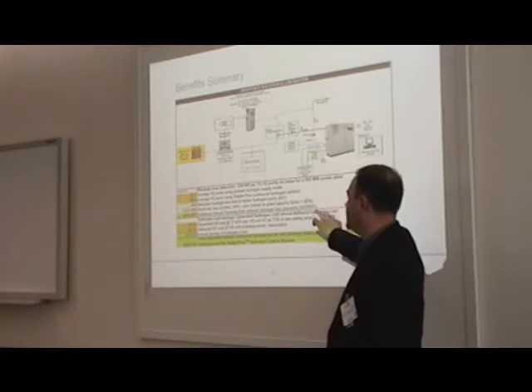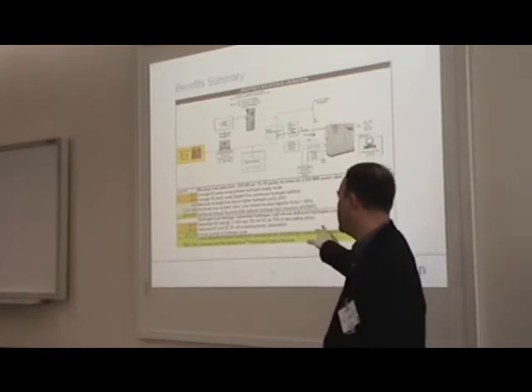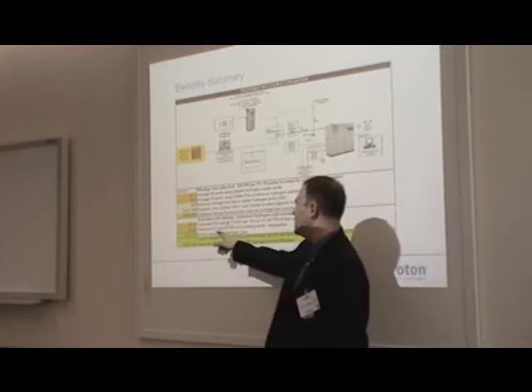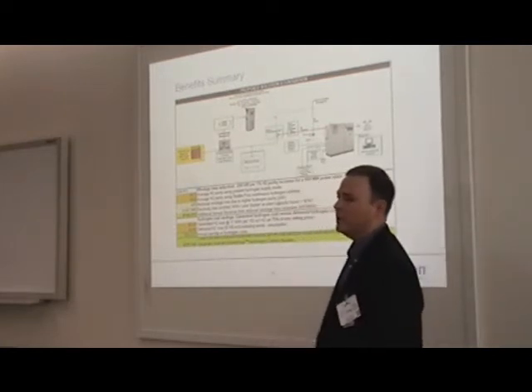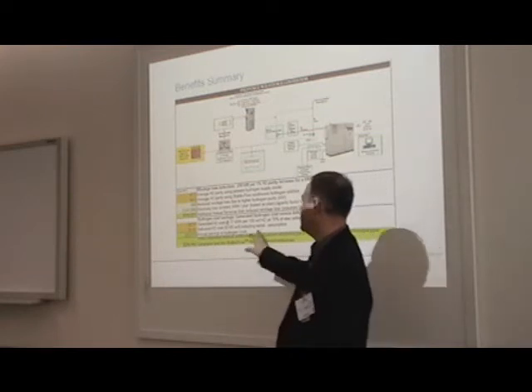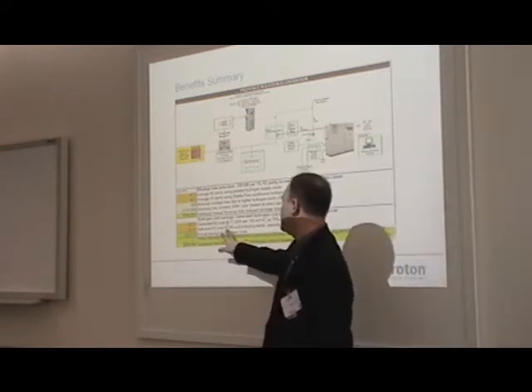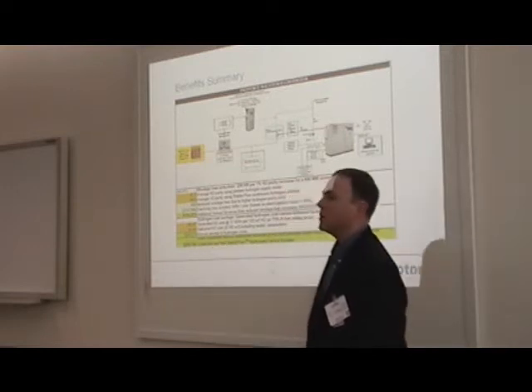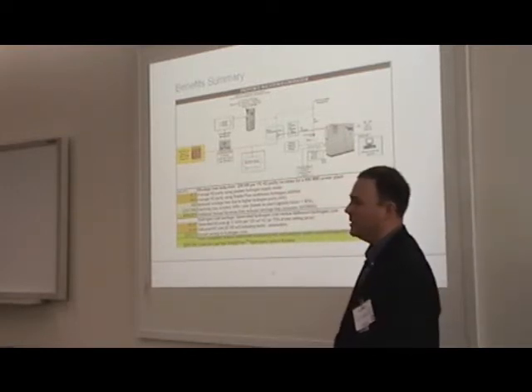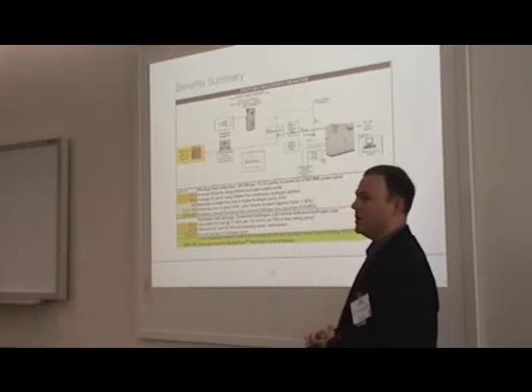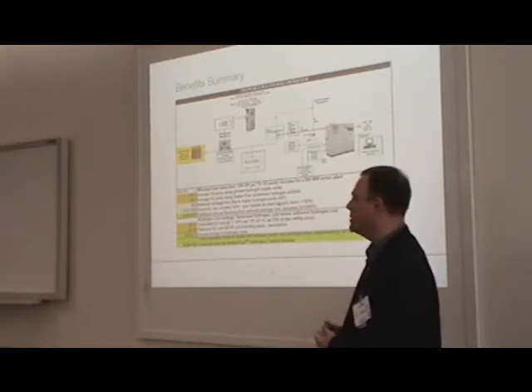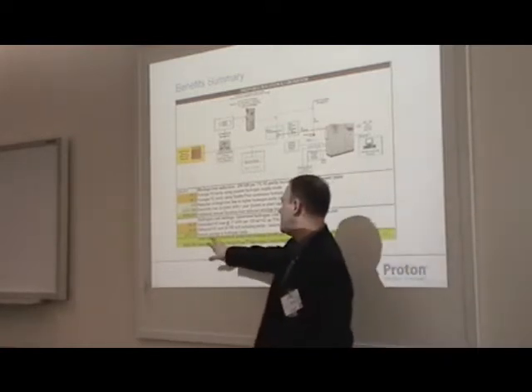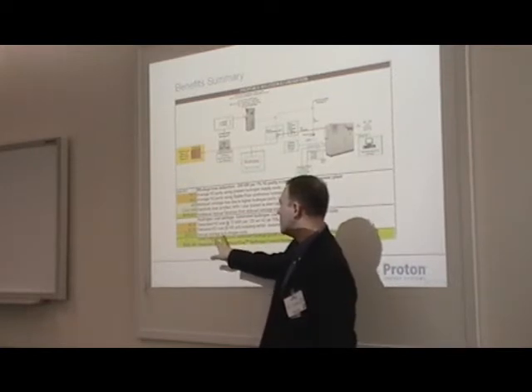We further looked at hydrogen cost savings for this facility. Generation costs at this site, using a hydrogen generator, are just under 60 cents per 100 cubic feet of hydrogen. They're paying $6 per 100, because this was an assumption based on the information we had at the time. There's a huge savings, 10 times savings in hydrogen alone. And to that, you can count all the safety benefits that, unfortunately, you can't always tag a cost benefit to, but certainly in the long run, it'll benefit the whole facility. So in this case, almost $50,000 in hydrogen savings over a year.